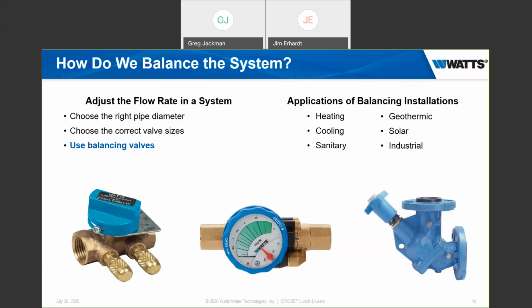That calculation is based on a couple of things. Number one, on the CV value of the valve, assuming that CV is perfectly correct and accurate. Number two, it also depends on the accuracy of the actual instrument. They typically need to be recalibrated once every year or so. And number three, sometimes there are calculations involved with variable orifice balancing valves, such as a CSM 61. There's a graph that needs to be used to input the correct information. So it's an estimation process. And really what that means is that we are estimating the flow based on pressure drop. We're not actually measuring the flow directly, kind of inferring what it is based on the pressure drop going through that valve.